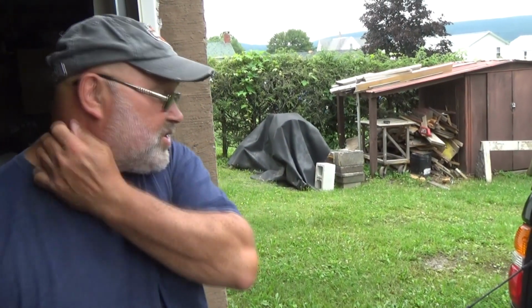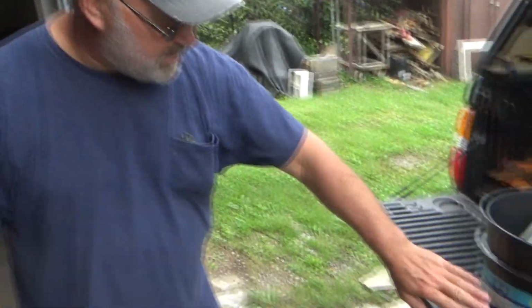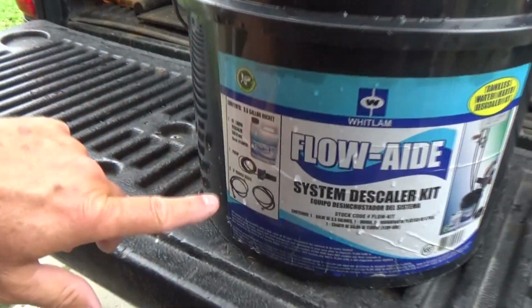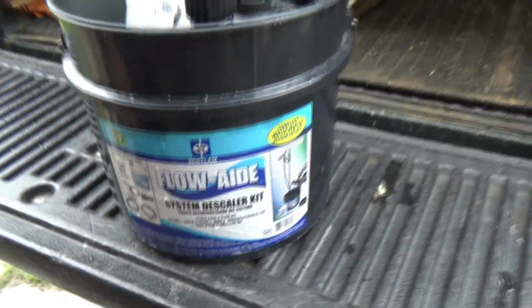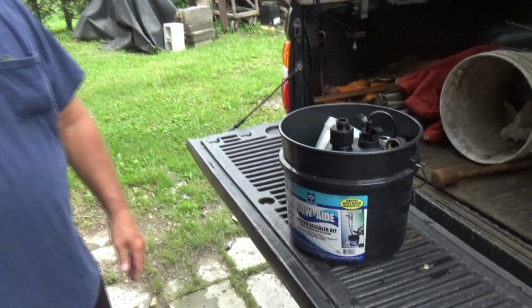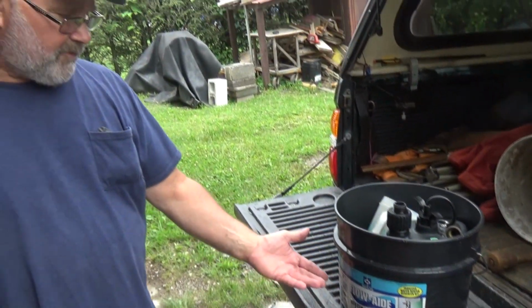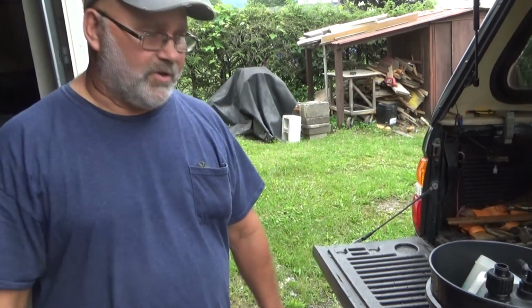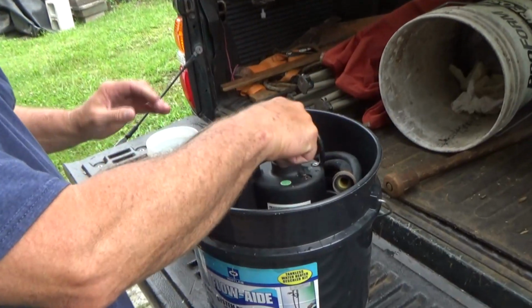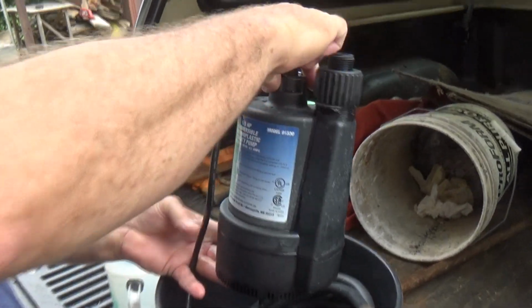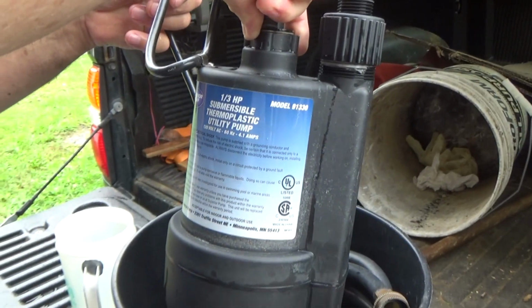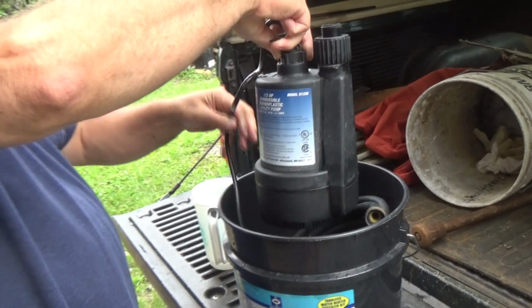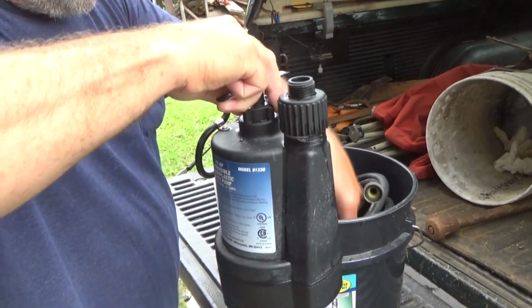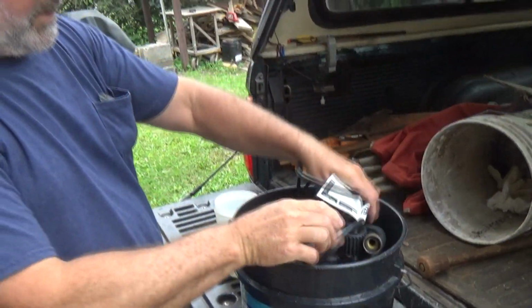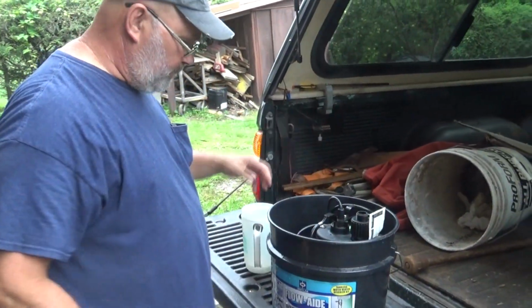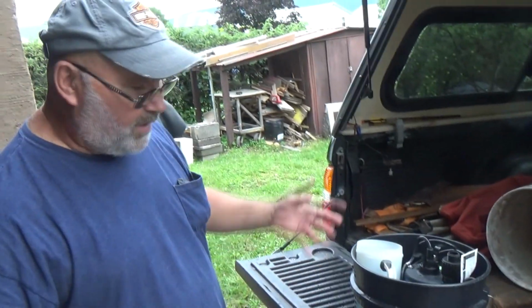When I originally started cleaning the tankless units, I bought this kit. It was a Flow-Aide kit. It included the solution, a pump, 2 hoses, and the bucket, naturally. But the pump would only last 2 years. I think there was a few-year guarantee, and I was able to get the first pump replaced. That lasted 2 years. So then I went to this utility pump, did a little research, and this utility pump is holding up real well. It's a Superior pump, 1/3 horsepower, submersible thermoplastic utility pump, and this seems to be holding up real well. The pumps that they give you with the unit are a little cheap thing, and it just didn't work out. So that's what I went to, and it seems to be working good for me. I just wanted to throw that in there.